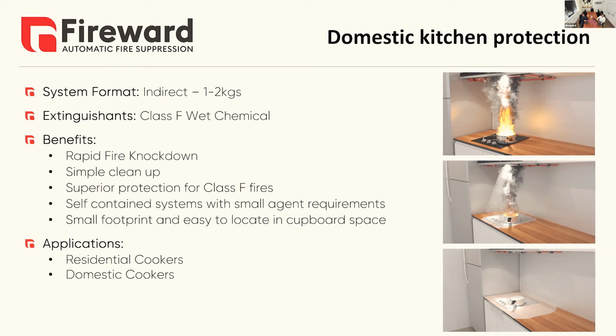We've got a video at the end to show you, but in essence what this system does is detect the fire from the hob using the same technology as the plant and equipment system shown earlier, scaled right down to detect a fire over a hob. We then use a specialist class F chemical, which creates a foam blanket over the top of the pan. We also have accessories that can switch off the hob and the ventilation above it, stopping the fire travelling up the extraction and stopping the heat source into the pan.